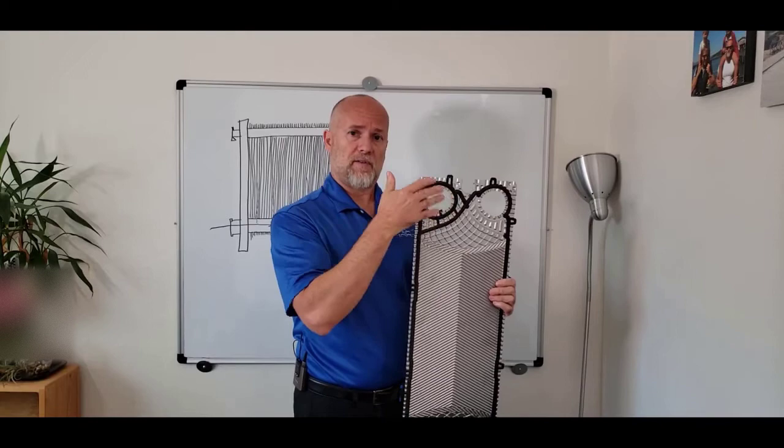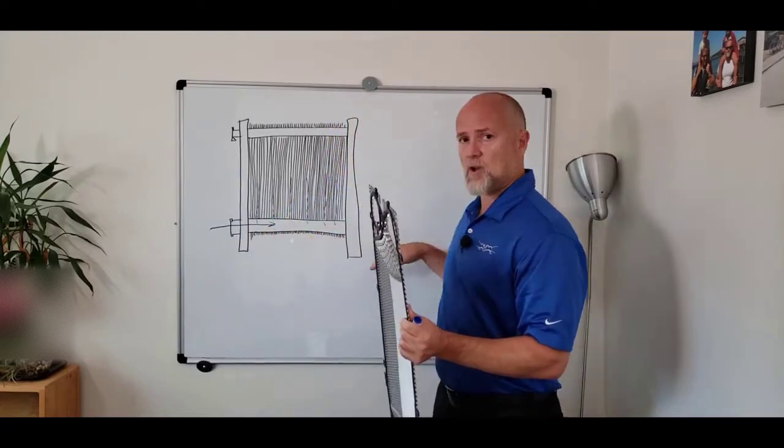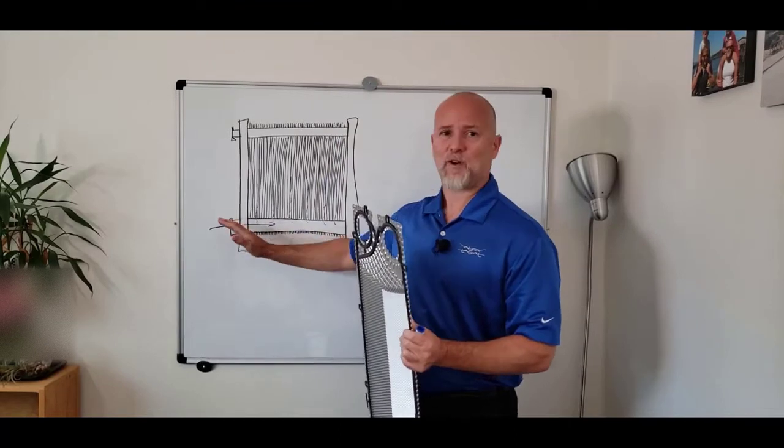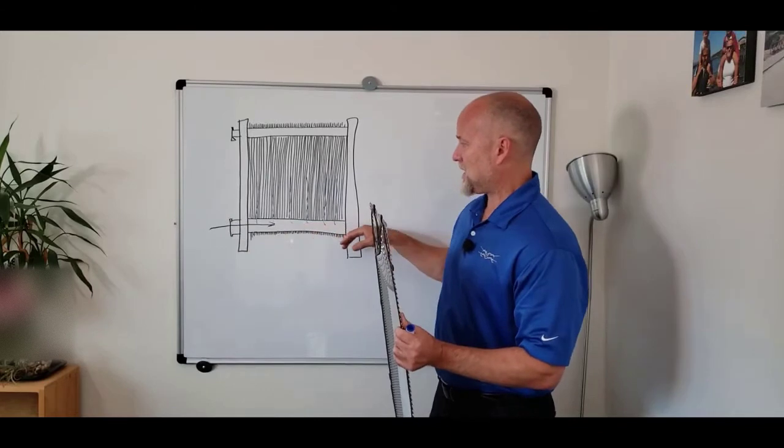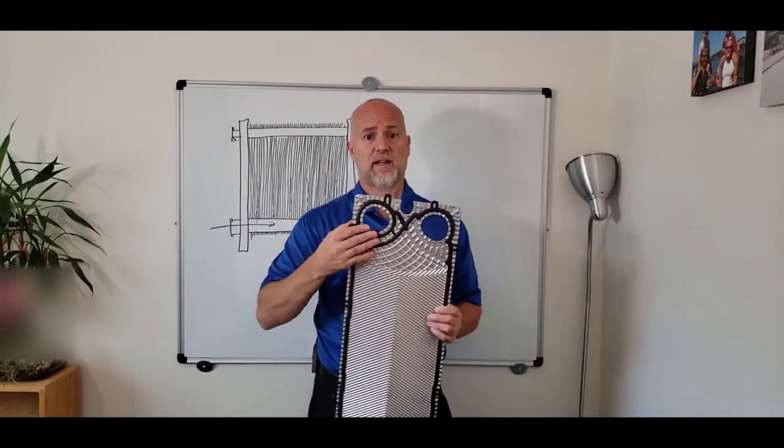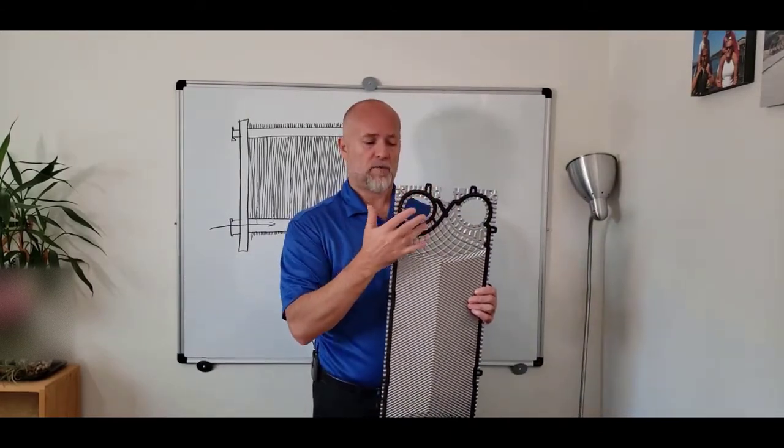This is to facilitate even distribution through the plate pack. Of course, the ports at the frame are round so they can connect with the piping. But inside the heat exchanger, the distribution is facilitated by the shape of this port.